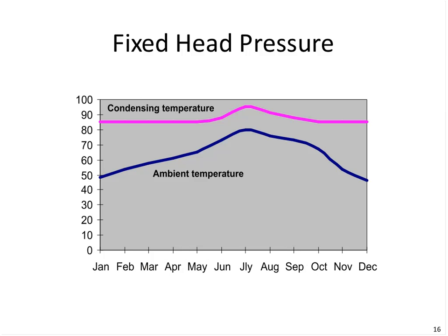Here's an example of what we call fixed head pressure. Of course, if we're not using the controls or attempting to attain these savings, we've got Mother Nature out here at 50 degrees ambient, and this could either be wet bulb or dry bulb, depending on whether you have evaporative condensing or not, but the idea is roughly the same. That ambient is low, say in the wintertime here, and we would still maintain a condensing temperature of, say, 85 degrees. Sometimes this is done for compressor design and oil separation issues. There are reasons why fixed head pressure is designed into the system.